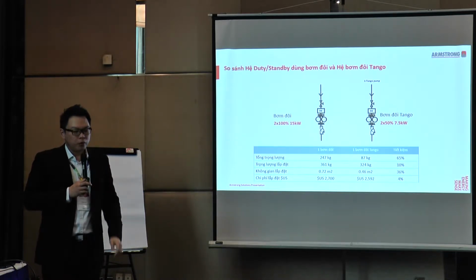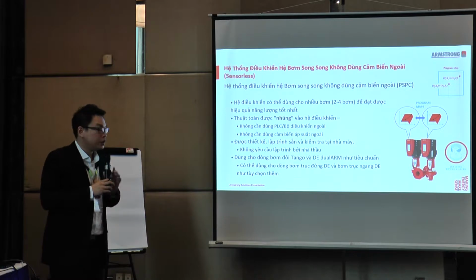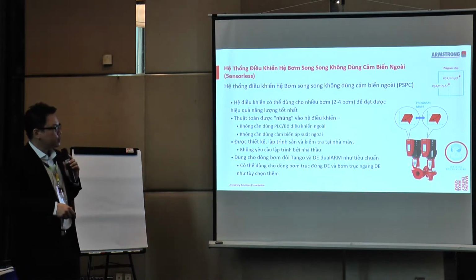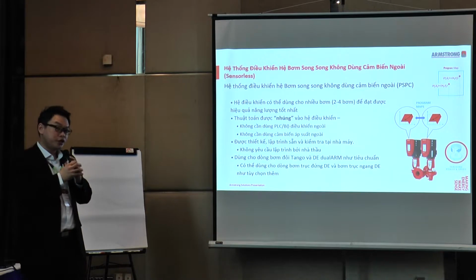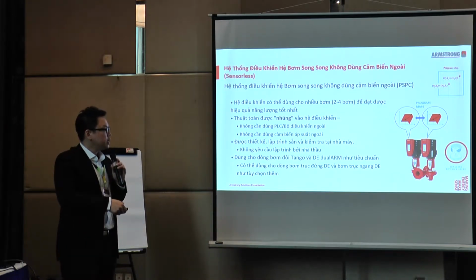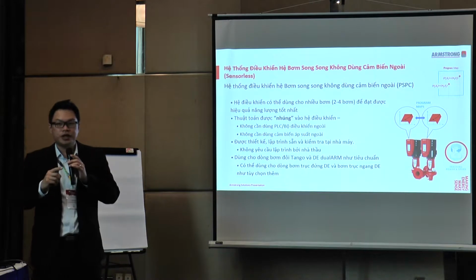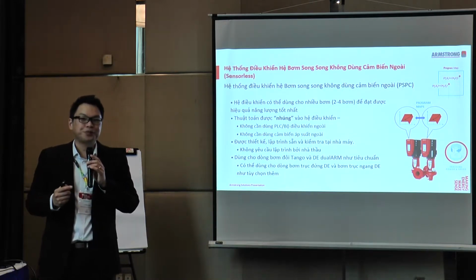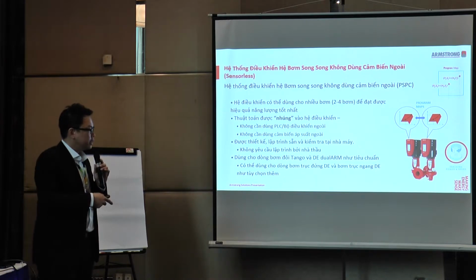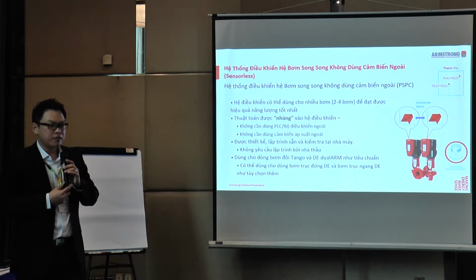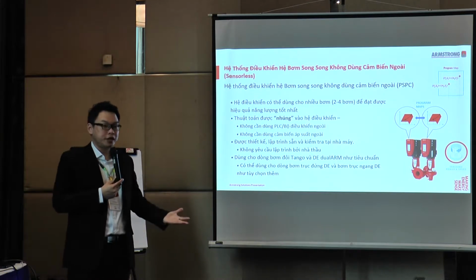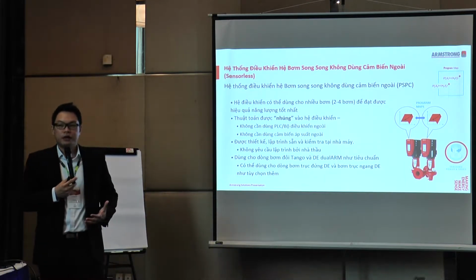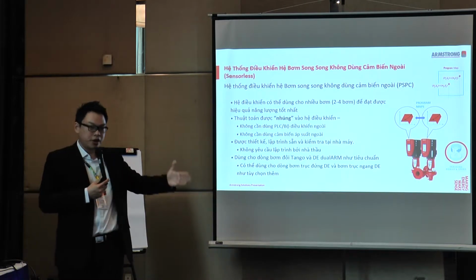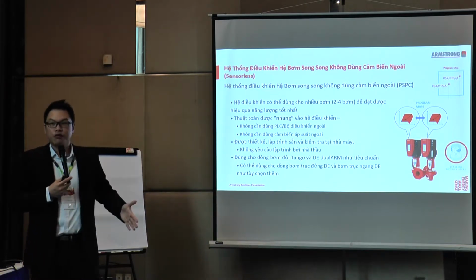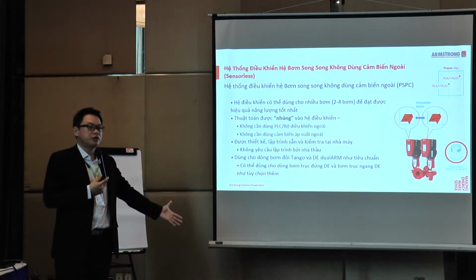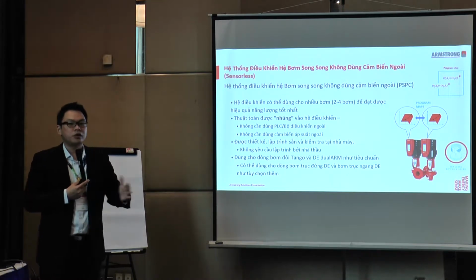Okay. Within our tango pumps, this is called tango. Why is it called tango? If you see, this is actually 2 motors with integrated drive, or VSD, and there's only 1 casing. What is interesting is that there are 2 impellers in 1 casing. Okay, and it's good because there are all the benefits that you have learned earlier. For example, redundancy is there, and when it comes to maintenance, you can just use a blanking plate to blank off one side and maintain it, while the other still continues to run. So there is no complete shutdown.